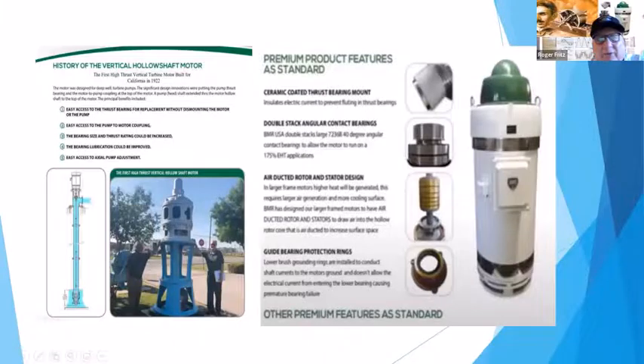Then everybody went through, okay, I want to downsize the motor, I want to make it, quote, more efficient. Well, they forget that we're actually in an environment that's not the real world, which is never balanced. So we don't have balanced voltages and powers and things. That's where they tend to not last as long. So this company went back to putting the bigger rotors back in them. They put the ventilated cores inside the motors, in the stator and the rotor, to make the motors run cooler.